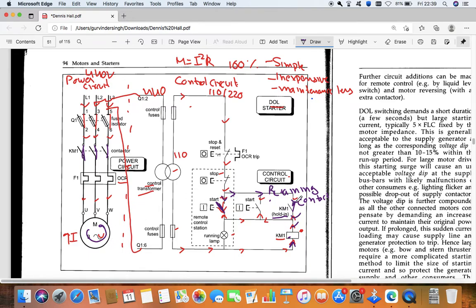If we don't have this retaining contactor, we press the switch, the motor will run. We release the switch, the motor will stop. But if we have a retaining contact, then our motor will keep on running. You just press and leave this start switch, our motor will keep on running. Now see here we have two start switches. One is local and one is for remote. You can start from remote also.